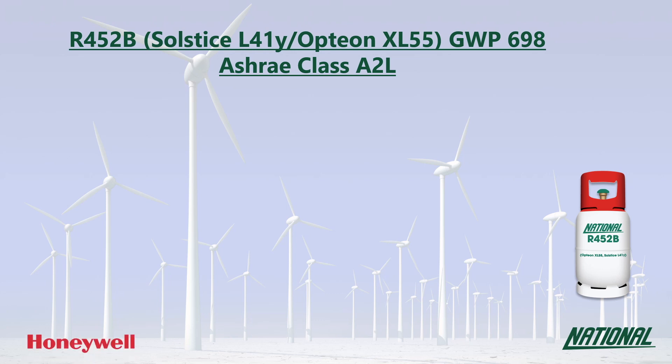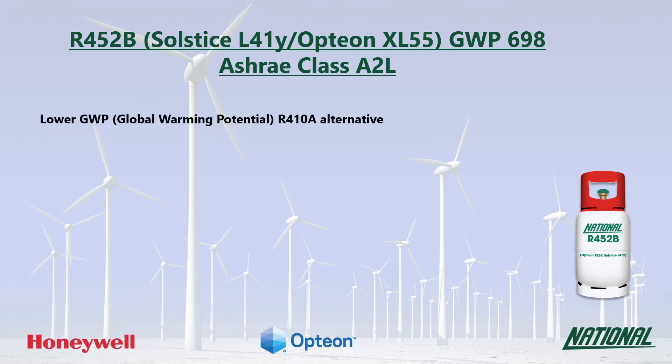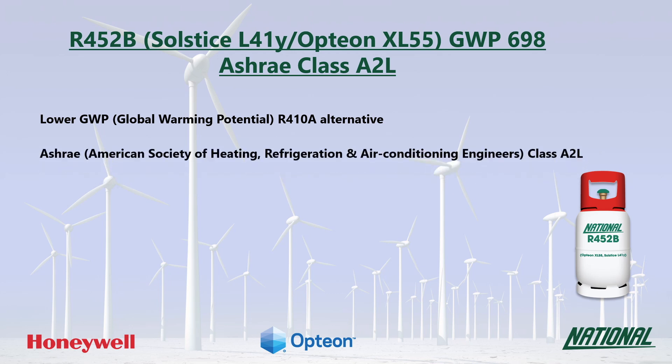R452B was developed by Honeywell and Chemours as a lower GWP alternative to R410A. You may also see it referred to by its manufacturer's trade names Solstice L41Y and Opteon XL55. Its GWP is 698, so at a third of the GWP of R410A, it is a much more environmentally friendly option and has been classified by ASHRAE as A2L, mildly flammable.